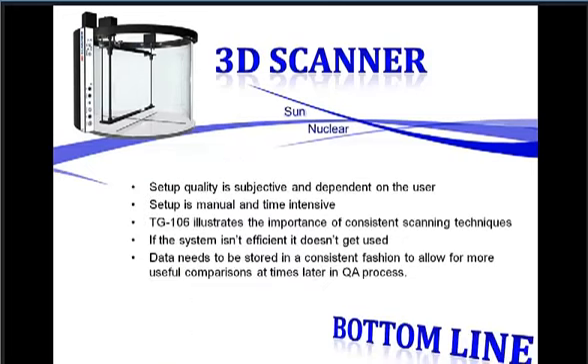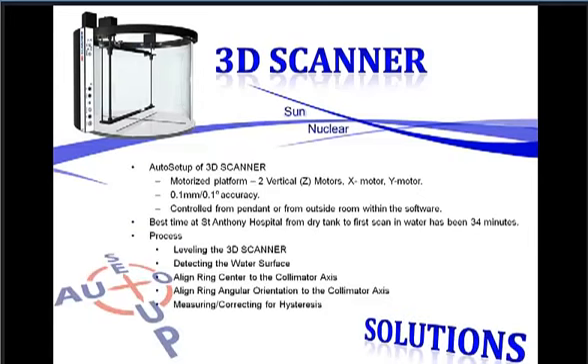It addressed the TG-106 consistency issues, as I'm sure we're all familiar with. The way it does it, eliminating the subjectivity of setup, is done through the auto setup functionality. I'll jump through a couple of these slides. The auto setup is a set of motorized platforms. It's got two vertical motors, an X and a Y motor. They quote 0.1 millimeter and 0.1 degree accuracy on the control of those motors and the alignment to the beam. We'll look at some scans where we've tested that during our commissioning. It's controlled either from a pendant on the tank or from a set of software routines and the auto setup functionality of the software, which you'll also see when we jump into the software. It levels the tank, detects the water surface, aligns to the center of the collimator axis, aligns the angular orientation to the field offset, and then corrects for any hysteresis in the scanning direction of the detector drive.